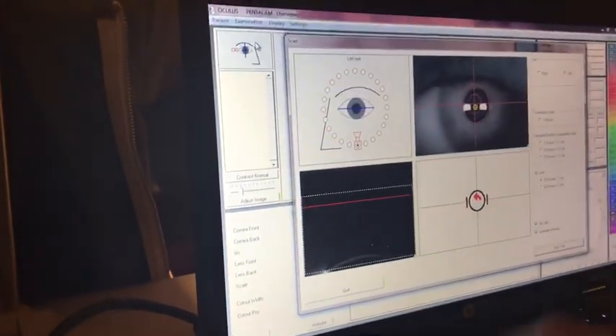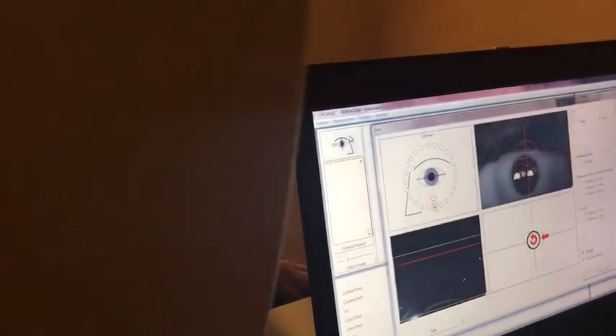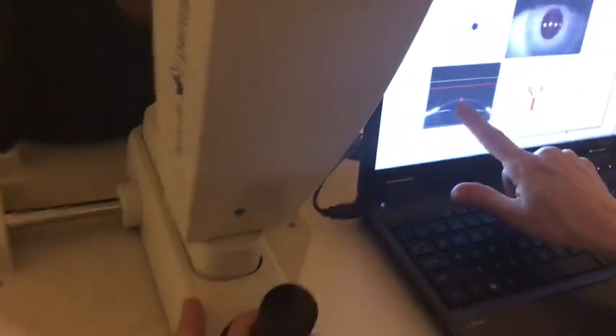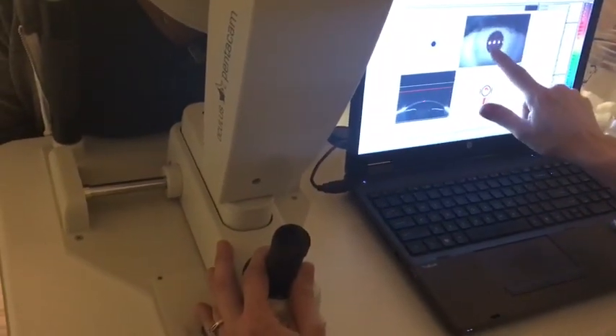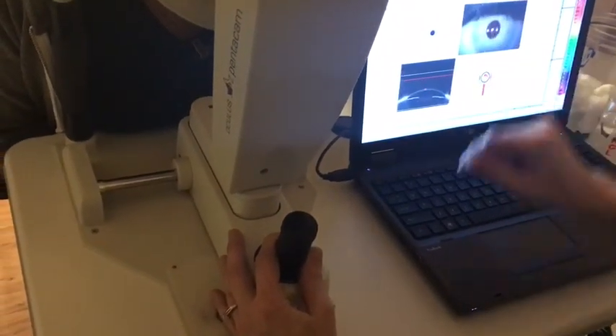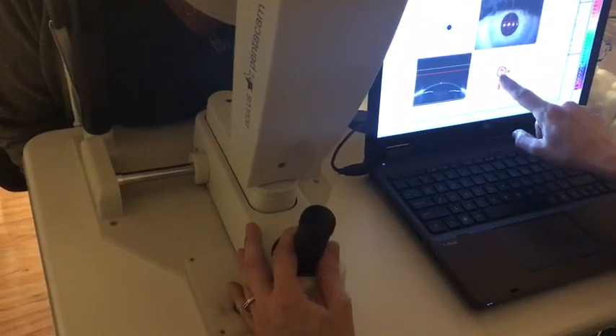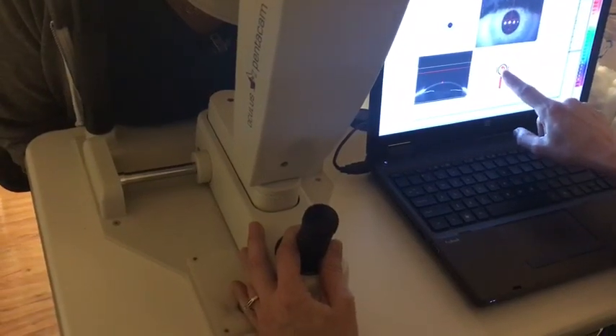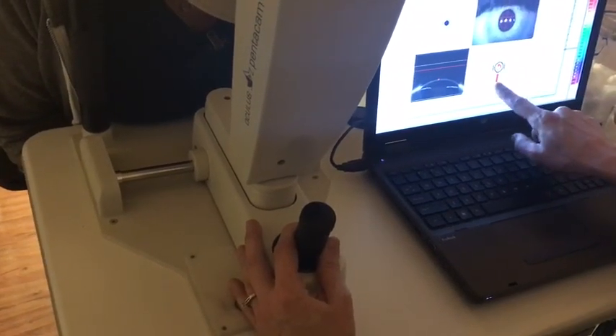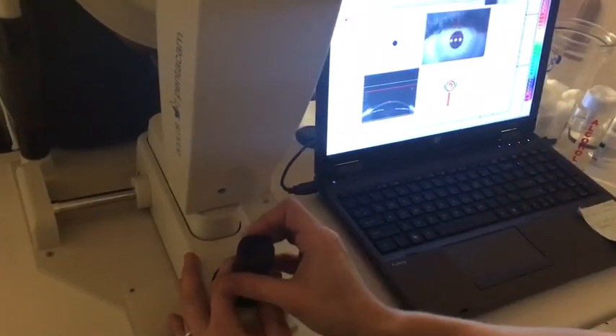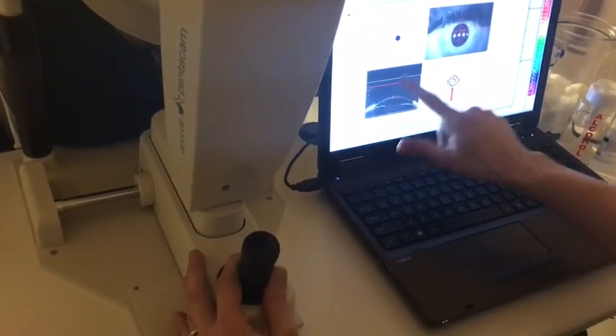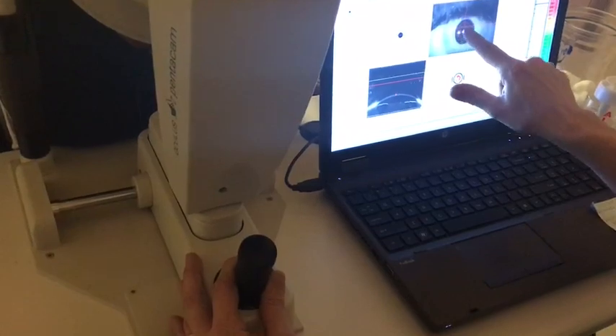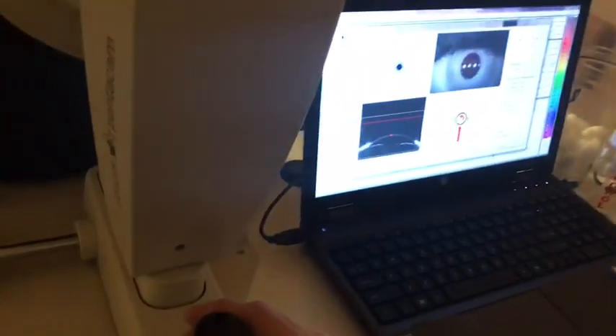And then you're going to look on your screen over here and you're going to move your joystick around until you can see the red dot. And you're going to put the crosshair right in the center of your pupil. And then you follow the instructions that it's giving you. This is telling you what the joystick needs to do and it needs to go forward and turn the joystick left. Once you get the red dot on the line and the yellow circle right in the crosshairs it will take her picture.